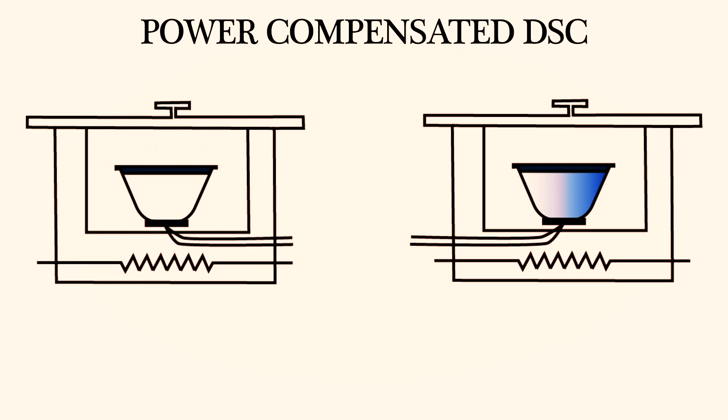Unlike the heat flux DSC, the power compensated DSC consists of two holders, one for the reference as well as the sample, each having its own sensors and heater. These two calorimeters are placed in a common block having a certain temperature. Platinum resistance thermometers measure the temperature. Next to the thermometers, two individual heaters are also built right below it to control the temperature.